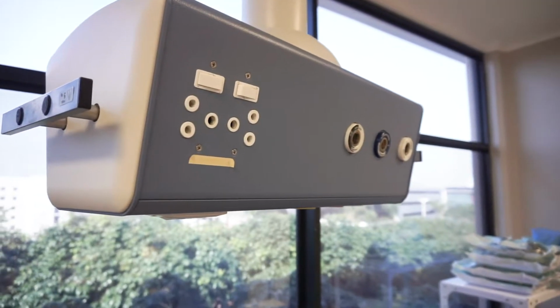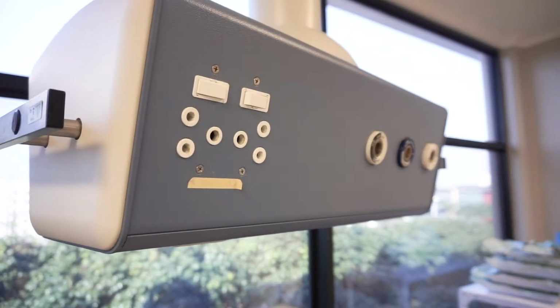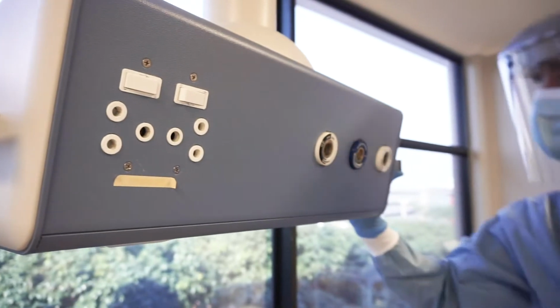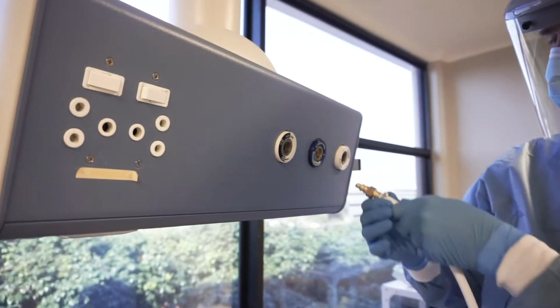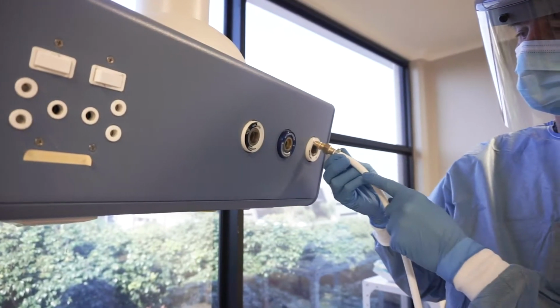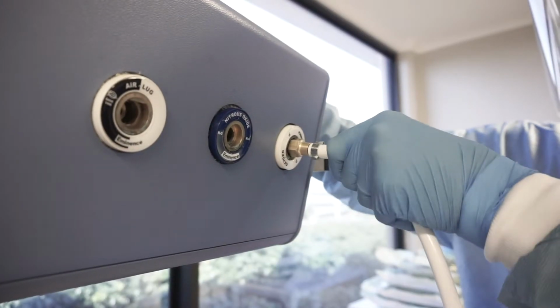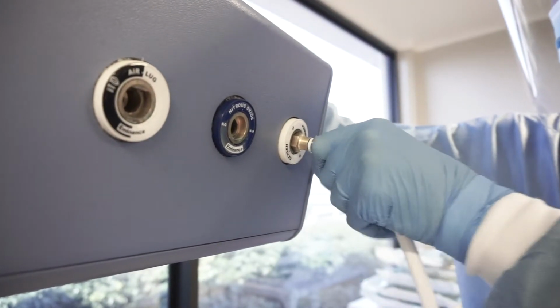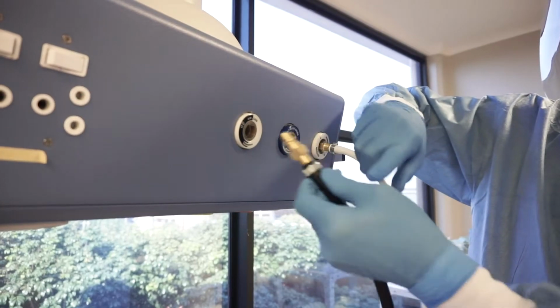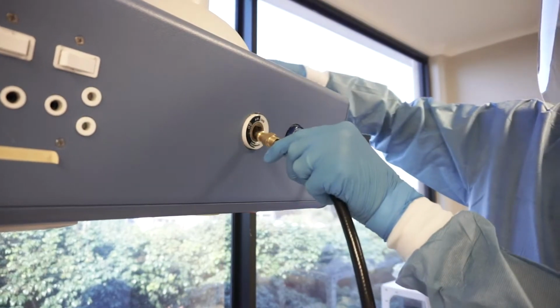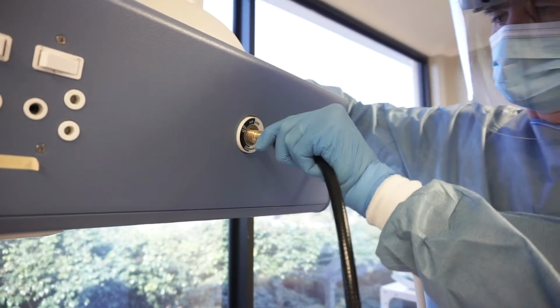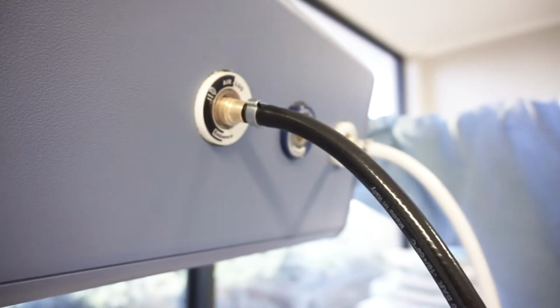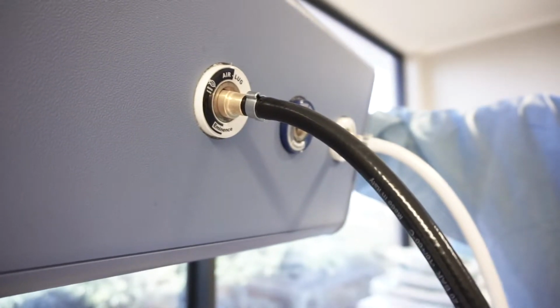You can now plug in the oxygen and air pipes into your wall supply. The oxygen is the white pipe and needs to be plugged into the labeled oxygen port on the wall. You must plug the medical air pipe, which is the black pipe, into the labeled medical air port on your hospital supply. Once you've done that, you're ready to set up the patient circuit, which you're going to put onto the patient.